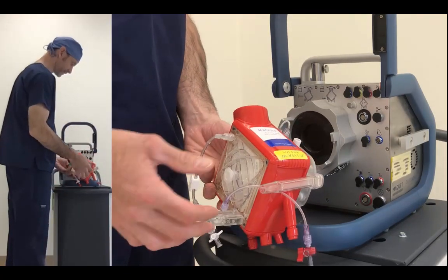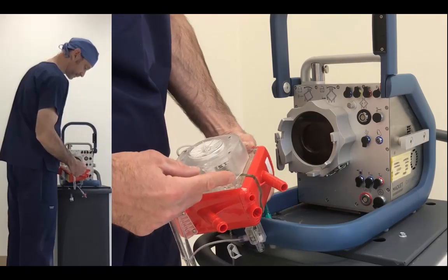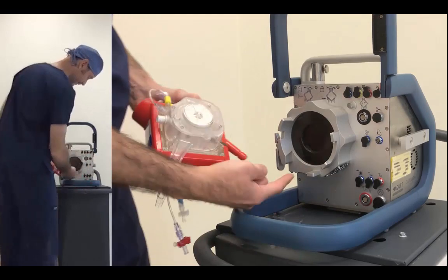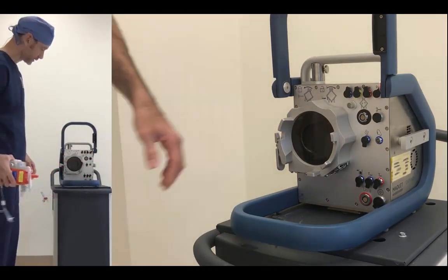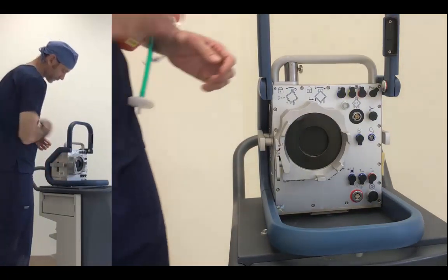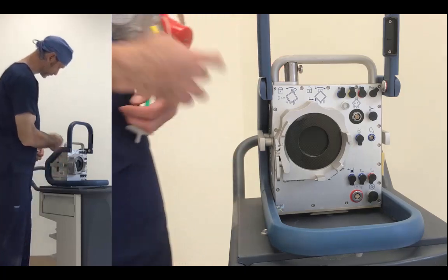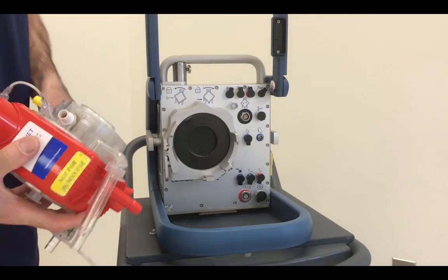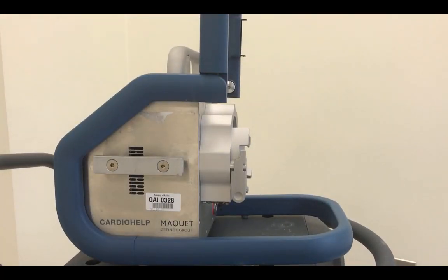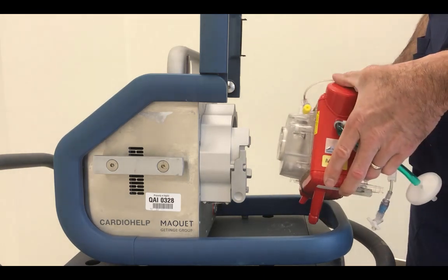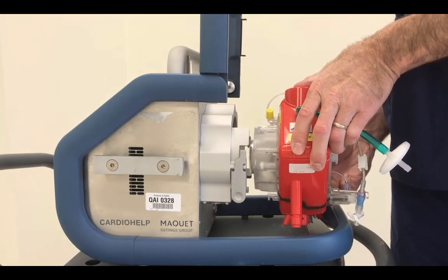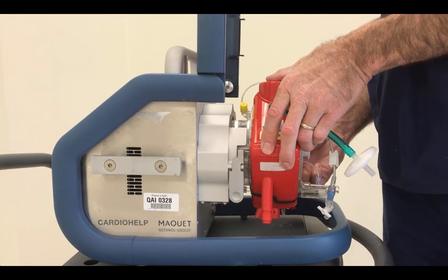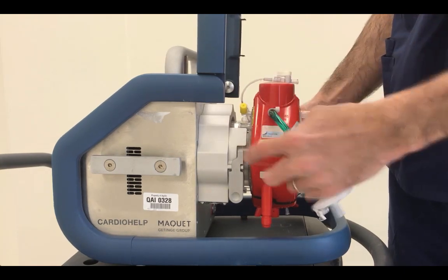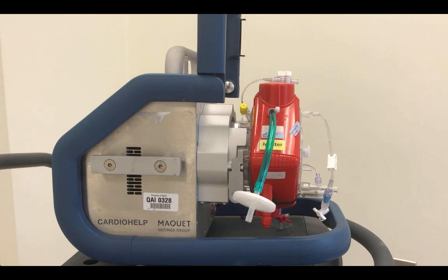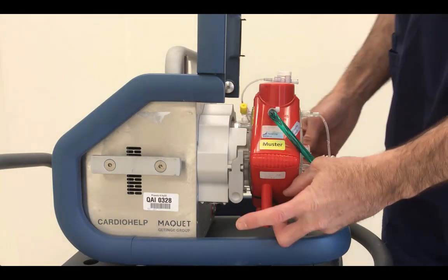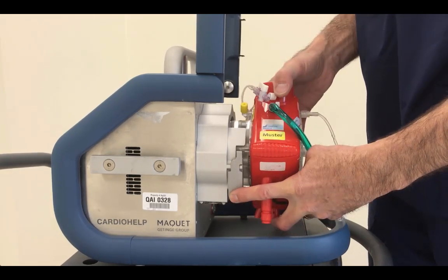This is an example of our disposable set. I've taken all the tubing off of it, and we can see that the motor is here. There's a loop on the bottom and there's a loop on the side that coincide with a pin on the bottom and the pin on the side, and this lever connection here, which presses in to secure and release the device. So if we're going to place this oxygenator in here, we approach from the side, tip just a little bit clockwise. When it looks like it's seated flat, tip it back, that latches in. To remove that, push that button in, rotate it back, and it comes right off.